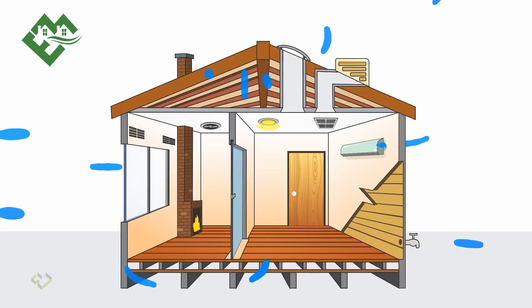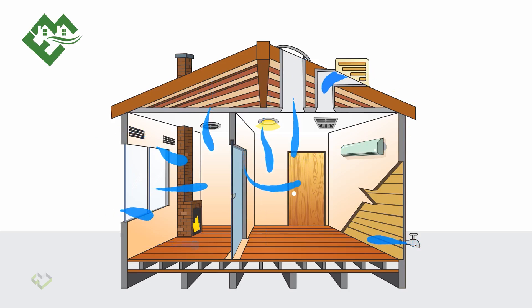For ventilation to work, you need an airtight environment that you're ventilating. For measurable, directed ventilation, an airtight building is way better than a leaky building. Because in a leaky building, you put good quality filtered fresh air into a room but you don't know where it will go — whether it goes through the wall straight outside, or leaks into other rooms. You have absolutely no control.